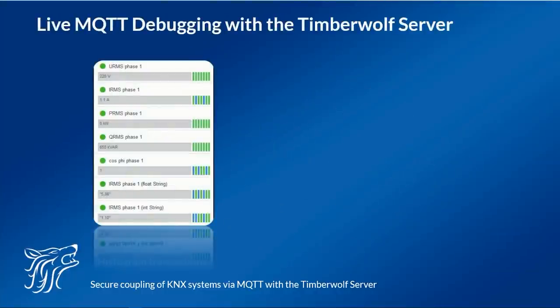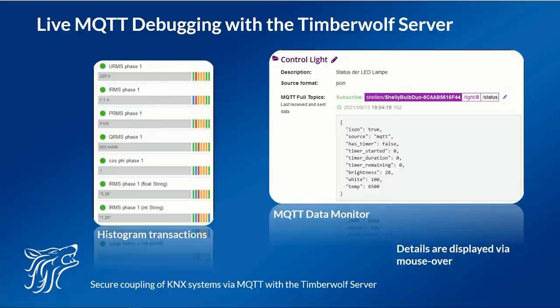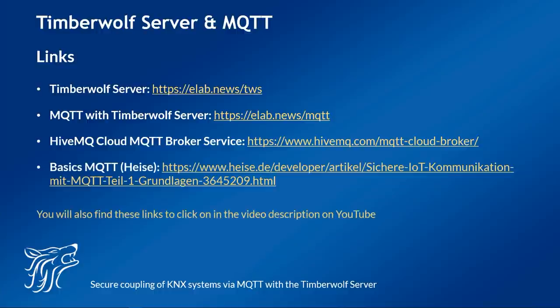Devices can become defective and even the best experts can make mistakes. In addition, data sheets of the devices involved are not always correct. The Timberwolf server provides displays and bus or data monitors for each of the supported protocols. For each transaction set up with an MQTT object, a histogram is displayed for trend analysis. To check the communication via the respective MQTT topic, a data monitor can be displayed with one click, which is updated live — allowing you to check the communication in real time. Details and recommendations for actions can be displayed simply by mouse-over, so you can find possible problems and errors in no time. More information can be found behind the links shown below in the description of this video on YouTube.